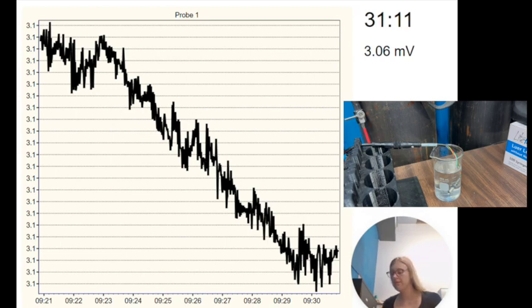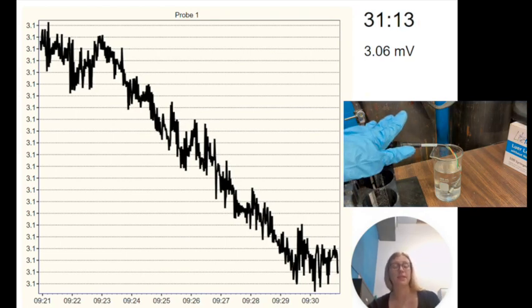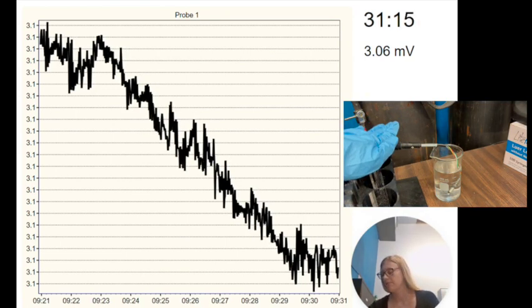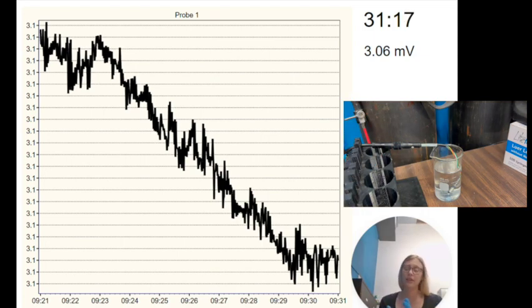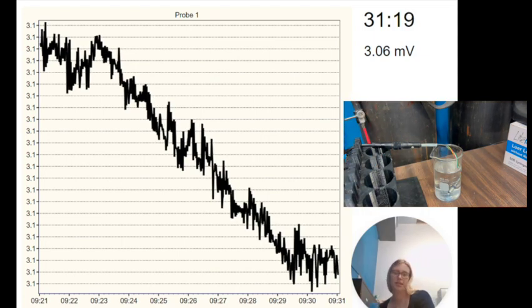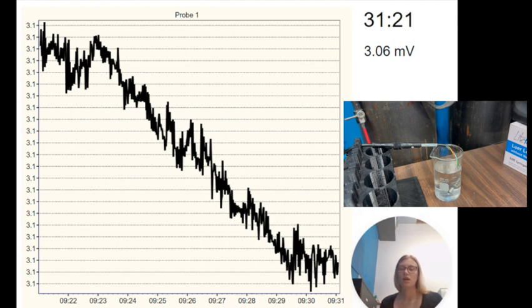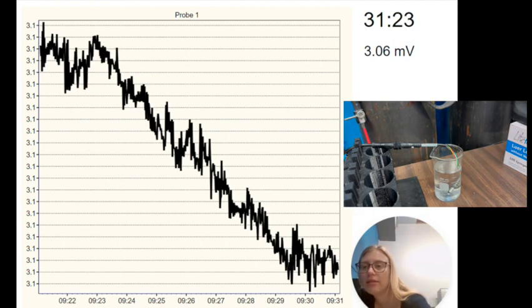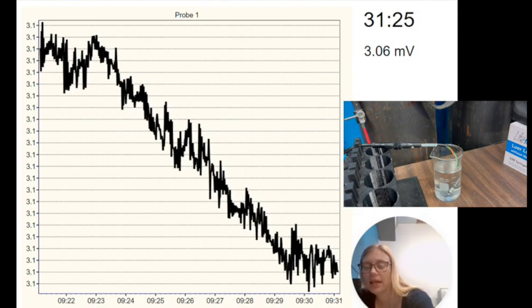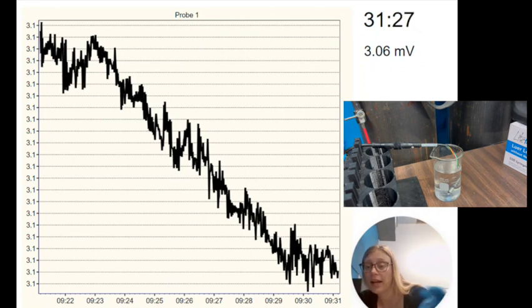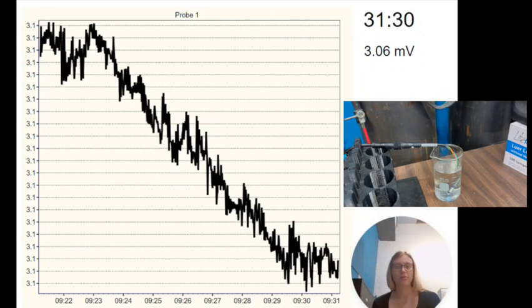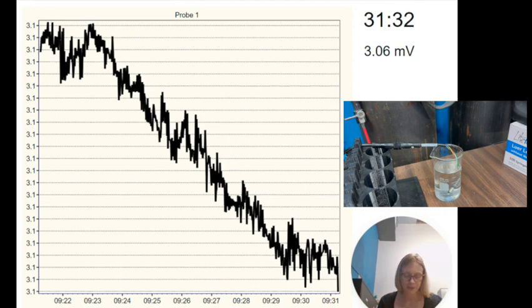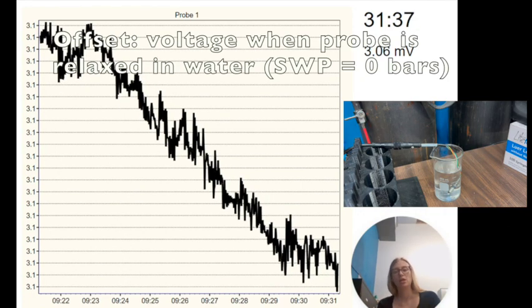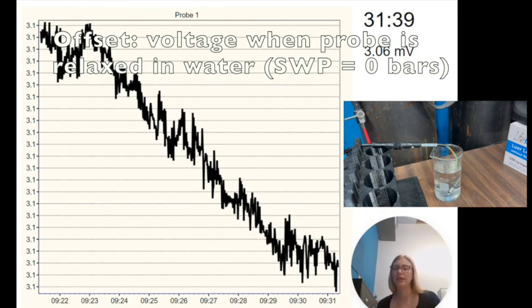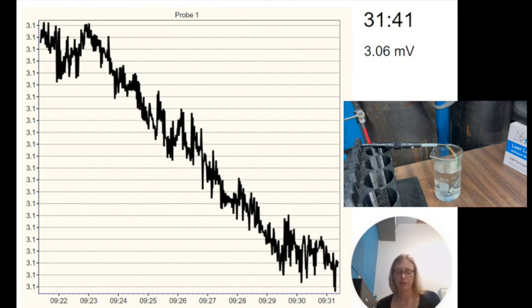All right, so we have this probe that we've recovered from the field, and it's been sitting in water overnight to clean the fouling, and then been relaxing in water for a while. So on the readout, we see with the scale on this side that it's relatively flat. It's not fluctuating very much from 3.06 millivolts. And that's what we would call the offset. So that's the measured voltage in water, and probes will read 0 bars at offset.